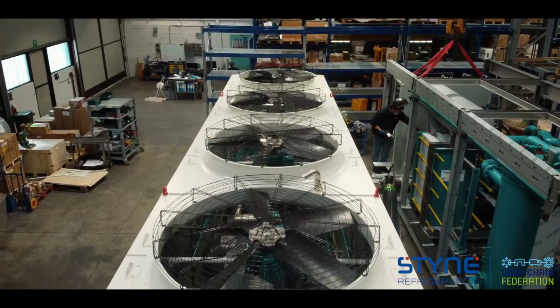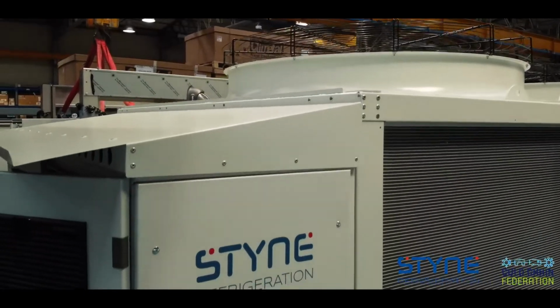That's good in as far as it goes. One of the challenges around that is all it is doing is driving your absorber. And there's the other side of the coin, as far as everybody who's got a business is concerned, the product is relatively expensive, with a relatively slow cost recovery period, return on investment, ROI. What's possibly a better solution, or a more usable solution for the next 5 or 10 years, is the implementation of a natural gas powered CHP engine, a combined heat and power engine, because instantly that will give you self-generated electricity at a price you can control, and you can use the heat from that combined heat and power engine to run your absorption chiller. So the return on investment figures on that sort of project are really quite prompt.